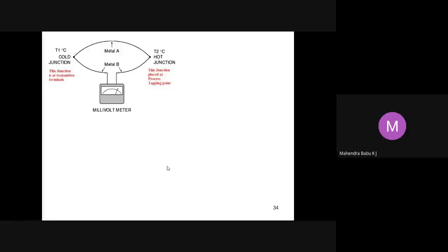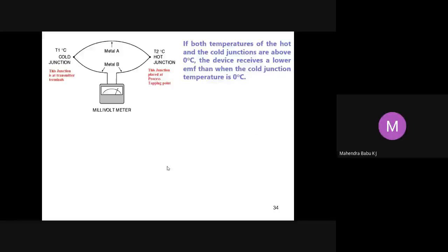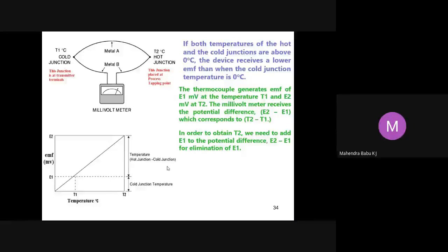In order to understand how the cold junction compensation works, let us consider temperatures T1 and T2, where T1 is at the cold junction and T2 is at the hot junction. If both the hot and cold junction temperatures are above 0 degrees Celsius, the device receives a lower EMF than when the cold junction temperature is 0 degrees Celsius. The thermocouple generates an EMF E1 millivolts at a temperature T1. Similarly, at a temperature T2, it will generate an EMF of E2.